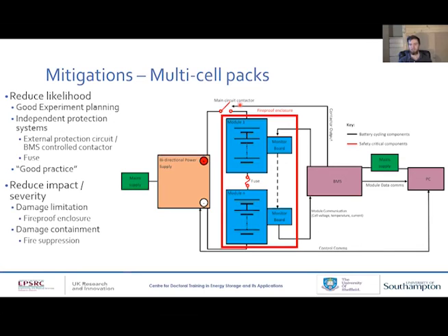The BMS will have measurements for voltage, current, and temperature for all the cells, and that sort of thing should be provided by a manufacturer. And so hopefully you should know it's reliable. If it fails, either the power supply for it fails, in which case the contactor opens because there's no power to hold the contactor closed, or if it fails in terms of communication, the PC can detect a discrepancy in the data between the power supply and the BMS.